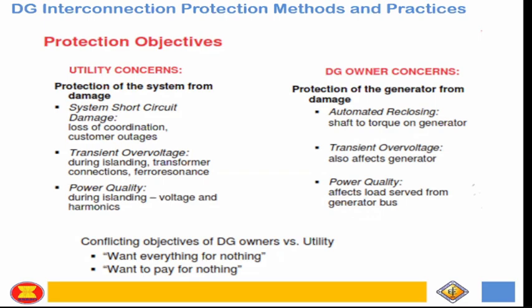Then addressing those, or improving those, through that automatic reclosing. But there's a potential risk for the DG, because if not considered, if there's no coordination and there's a fault, then it will reclose and your generator will still be running, and then it's not isolated. The coordination should ensure that the DG is isolated when you reclose the recloser. So their generator will be damaged.